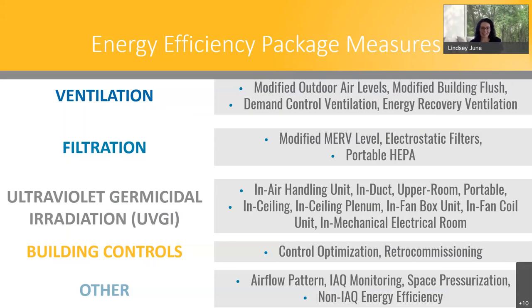There were several applications for UVGI air treatment that were evaluated, the most prominent being an air handling unit, which is typically placed near coils or filters. In duct, where there are typically long runs of duct that provide lots of room for UVGI. Upper room, which are wall-mounted fixtures, typically installed 7 feet or higher, and the rays extend upward to treat the upper room air, and there's no direct contact with occupants. Ceiling mounted is typically an enclosed unit with a fan that circulates air through for treatment. In ceiling plenum, or mechanical electrical room plenum, where the plenum acts as the air mixing zone, low air velocities make them a good application. And then in fan box units or in fan coil units, there are small devices that can fit within these units and be effective.